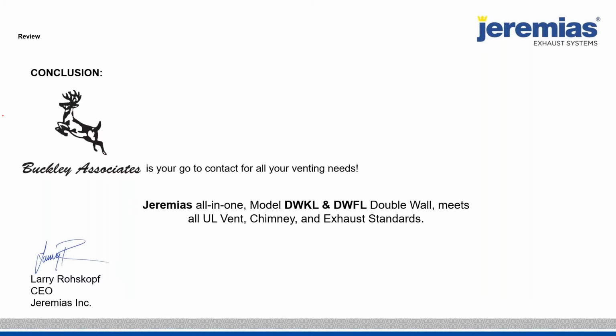Go ahead. So we do quite a bit of public work. Requires us to list 3 manufacturers. So, what would be the appropriate competitors, or is there anyone else that can kind of meet the same requirements? Well, what we try to do is educate to think about the exhaust systems to be all stainless steel construction like they are in Europe, because they require no maintenance. So if we compete with Selkirk, Van Packer, Metal Fab, Schebler, but if you specify the fiber insulation between the walls to always have that man-safe temperature, if you specify a stainless steel outer jacket, this is our standard product. We're competing every day with all stainless steel compared to a galvanized outer or aluminized outer spec.